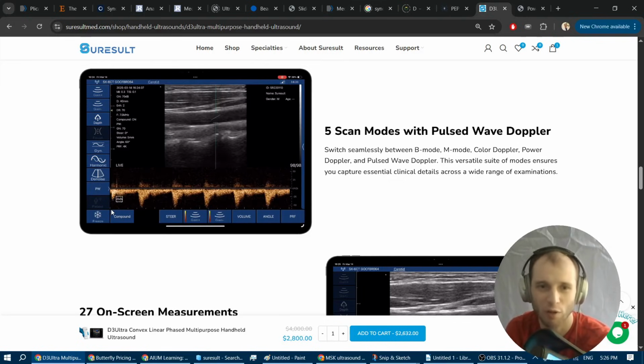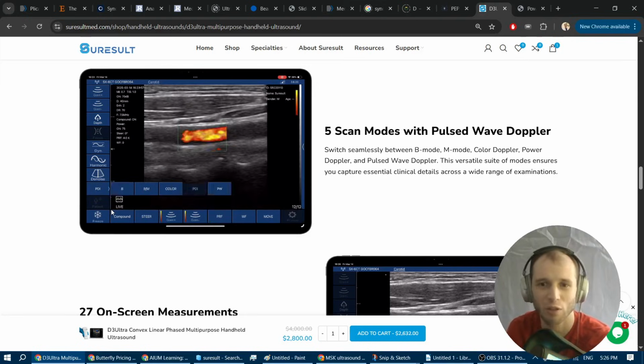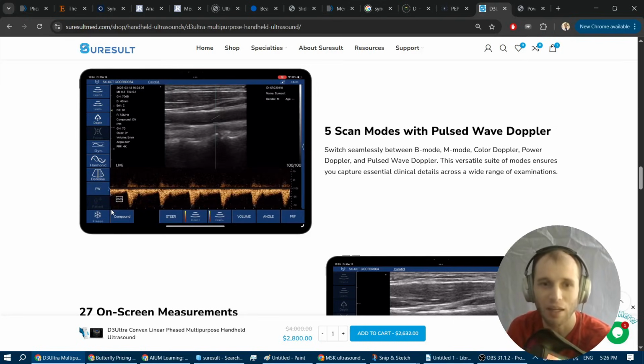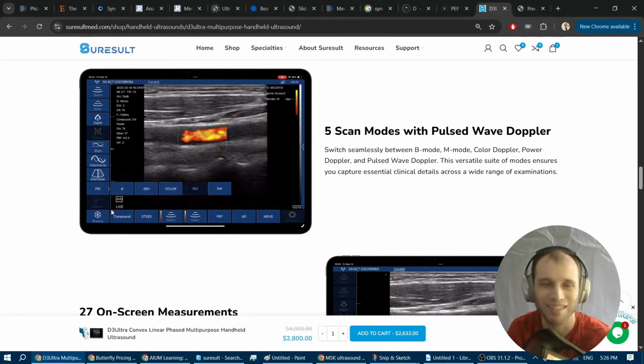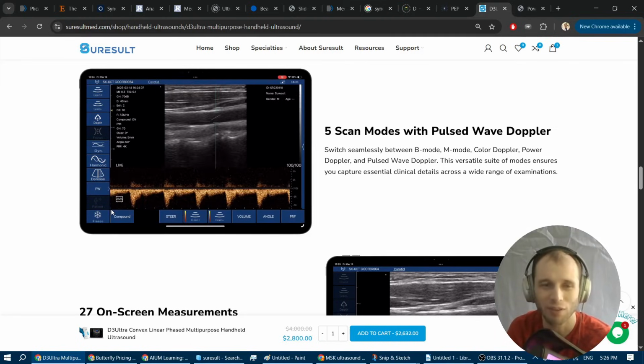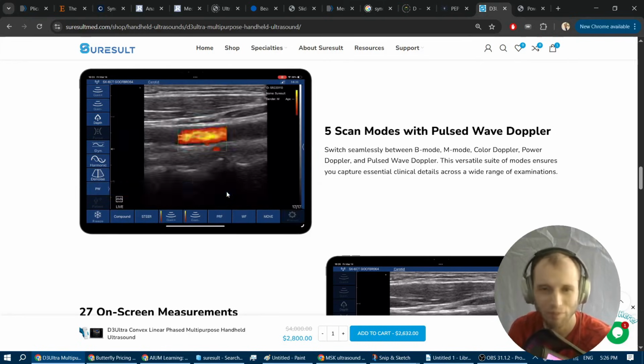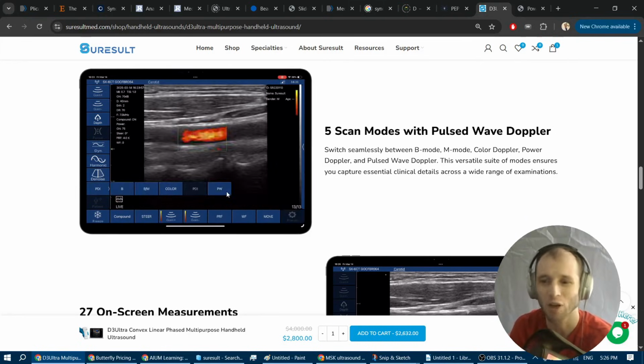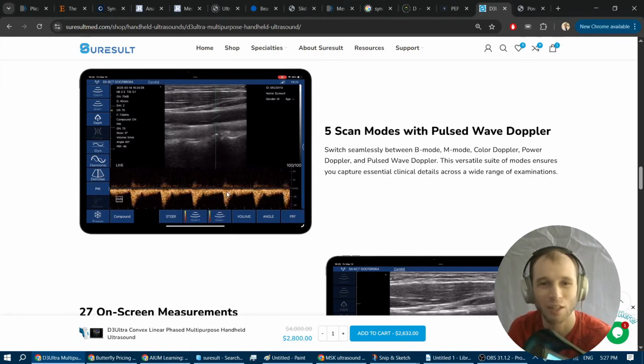You want to turn this off for MSK because compound imaging is going to reduce the frame rate greatly, and the benefit for MSK isn't worth it. And sadly, it seems to be on by default in the newest update to the app. The other thing about updates to the app, you have to go into the store and manually download the newest version. So it won't interrupt you or stop you from scanning a patient. It really is a very, very simple program.